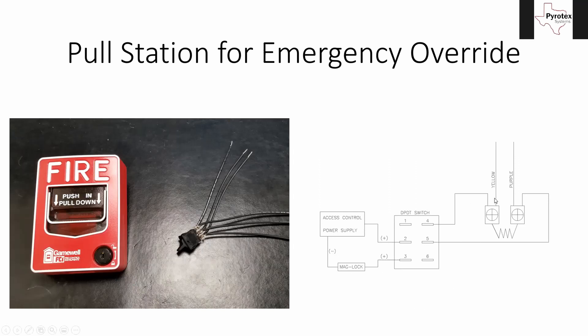In normal operation, contacts two-three and five-six are closed: power comes in from access control, goes across the closed contact to power the lock, and returns on the negative side. Everything works normally — lock is on, alarm is off. When the pull station is activated and the switch flips, one side closes and the other opens. The fire alarm side shorts from terminal four to five, bypassing the resistor, causing the short circuit that tells the monitor module there's an alarm. And the formerly closed contact that powered the lock opens up, turning off the lock so the trapped person can get through the door to the stairwell and safety.